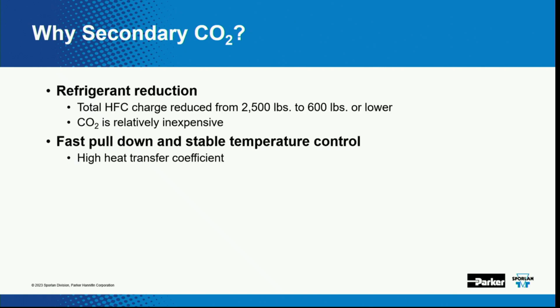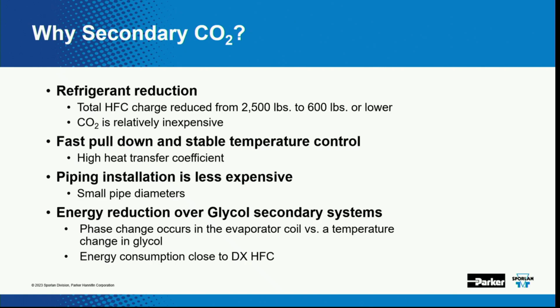Oh, I've got this question here - why secondary CO2? Again, to reduce the total HFC charge in the system, it could be dropped by an 80% reduction. CO2 has a high heat transfer coefficient, so we can get a fast pull down with CO2. CO2 also has smaller pipe diameters, so it's pretty easy to run that stuff, and it's less expensive to install. It's a win over glycol, because remember I said the glycol has a pretty big energy hit to circulate it in the system - with CO2, not so much.